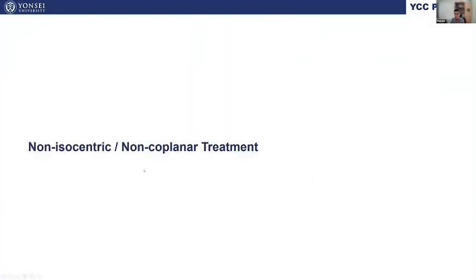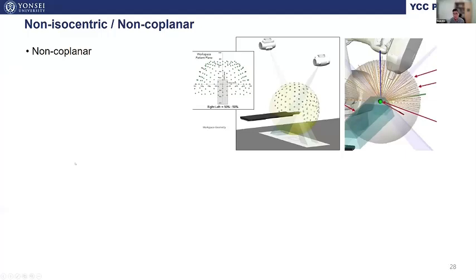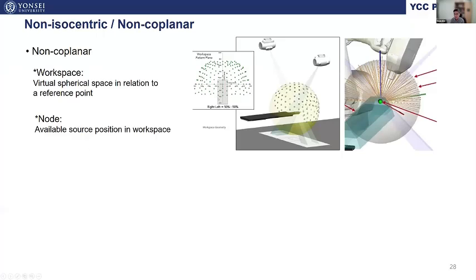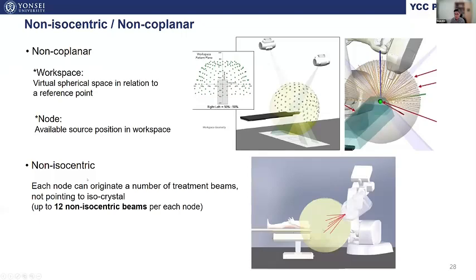Next, the non-coplanar and non-isocentric features of CyberKnife will be specified. Workspace means a virtual spherical surface which can be generated relative to a certain reference point. As a matter of fact, although CyberKnife is a non-coplanar treatment unit, it's not true that all spots within the workspace are available for the treatment. Only specific points defined as nodes are supposed to be assigned around the reference point. Also, it is important to be aware that each node on the workspace allows for a maximum of 12 non-isocentric directions, which is not an infinite number. Thus, the key issue to discuss here is how to define the reference point, determining the workspace and nodes.